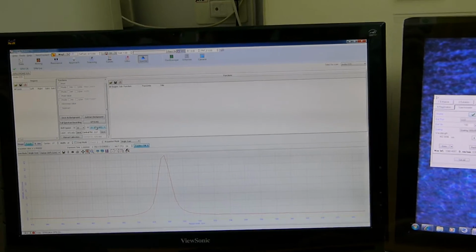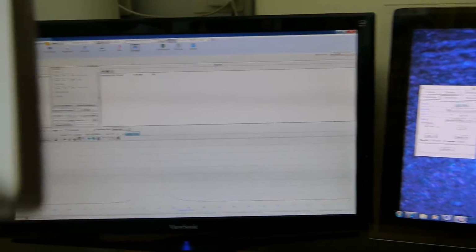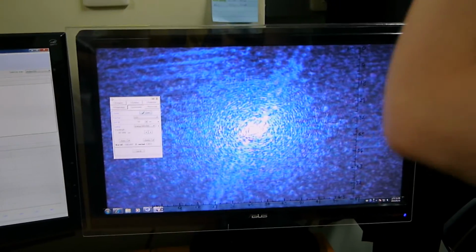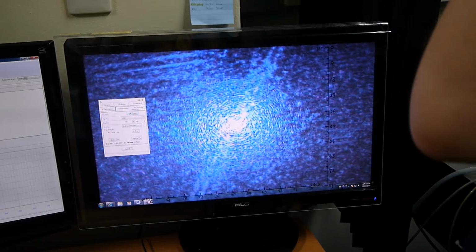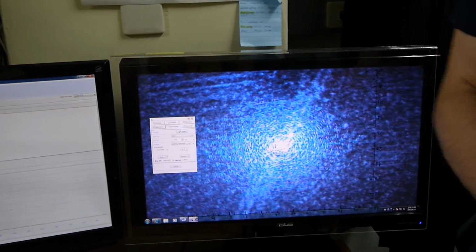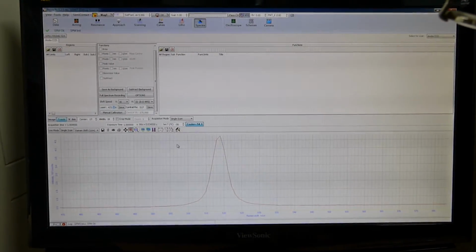For example, you change the laser wavelength a little. The laser is a 473 semiconductor wave, and 473 can be 473.0 something. It can shift. I met sometimes a shift of 0.1 nm or more. Such a laser depends on temperature. For example, if we switch here to 0.1 nm, enter.